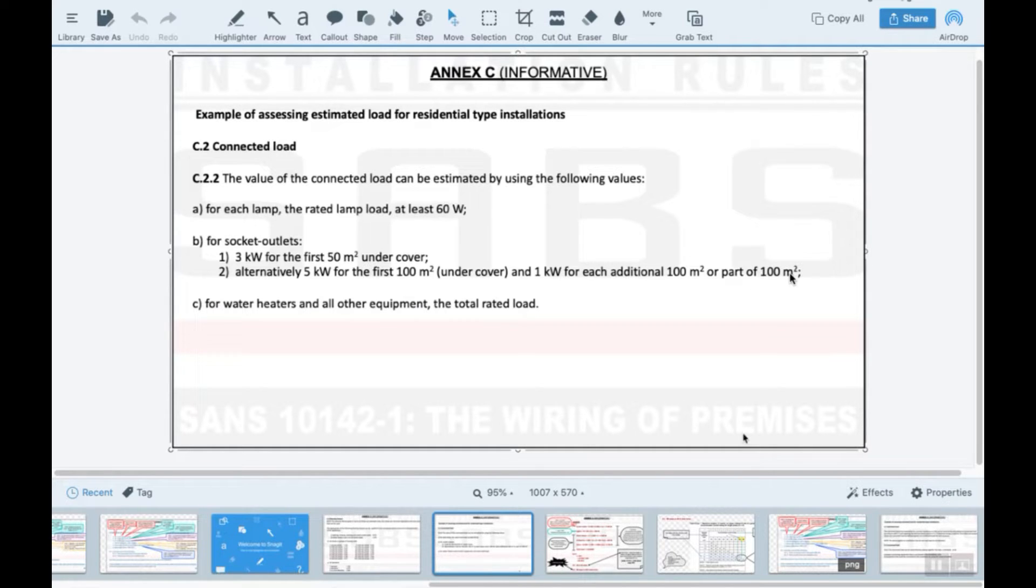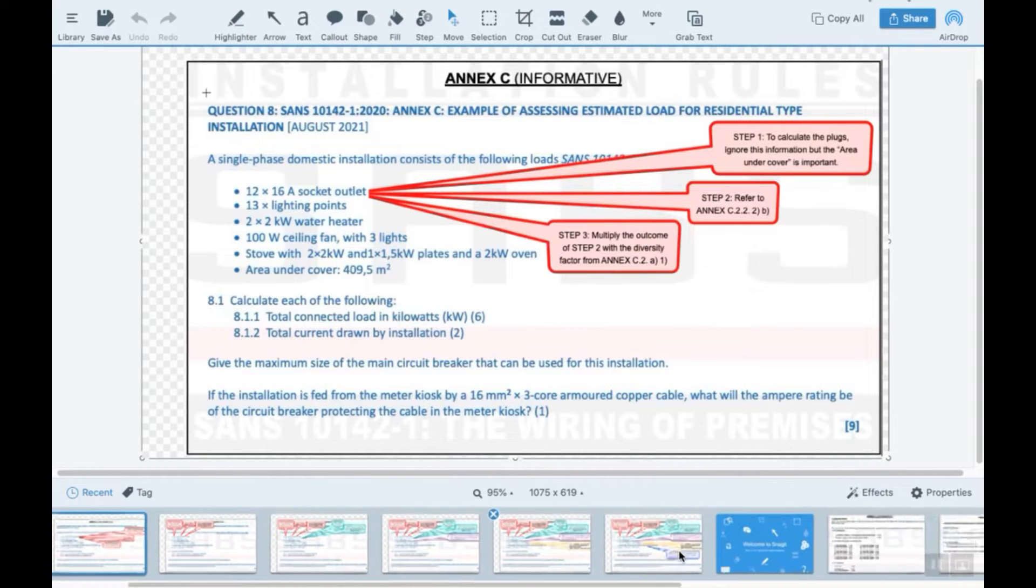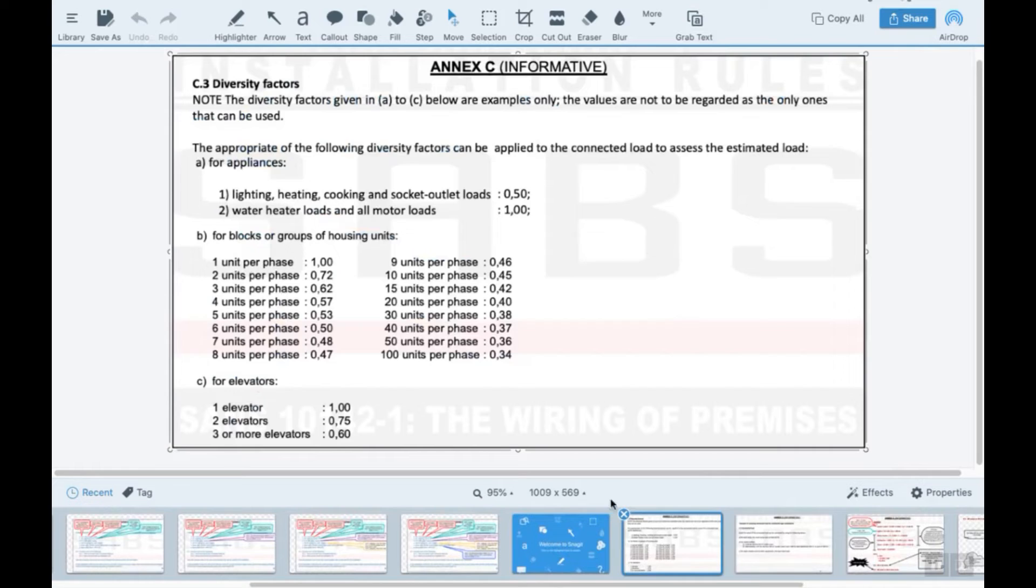Going back to that slide, step three: after you've applied this part to the floor area for plugs, then you must multiply that by the diversity factor. Diversity factor also found here, and it is clearly diversity factors. This is from the SANS book: lighting, heating, cooking, and socket outlets. So the diversity factor would be 0.5.